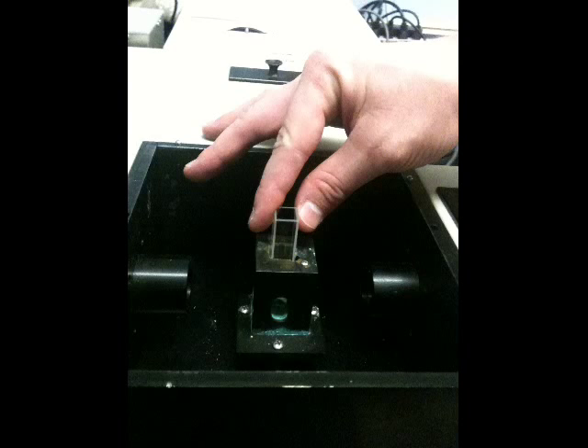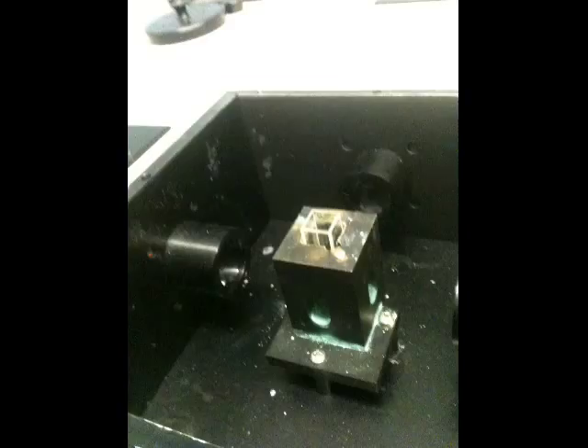Once the sample is bombarded with the radiation, the analyte will jump to an excited state. Upon being in the excited state, it will relax back down, giving off fluorescence, which will then go through the tube right there to the right side or left from this view, and from that tube it will then go into wavelength selector number 2, where this wavelength selector will select the appropriate wavelength that gives the maximum reading of emission from the fluorescence.